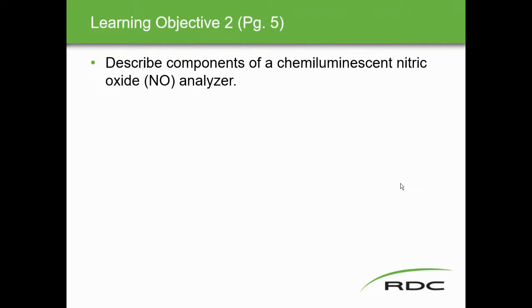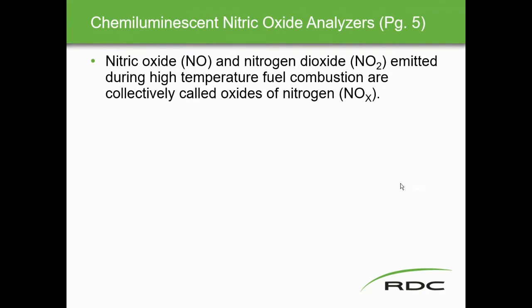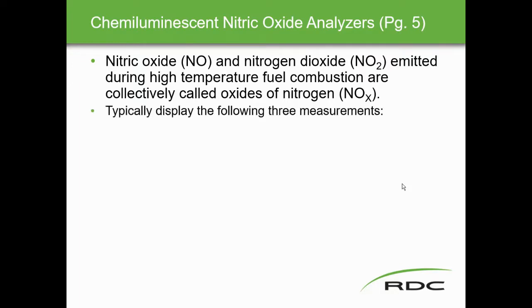Learning objective two: describe components of the chemiluminescent nitric oxide analyzer. Nitric oxide and nitrogen dioxide are emitted during high-temperature fuel combustion in stacks, and are collectively called NOx — oxides of nitrogen. The analyzer typically displays three measurements: NO (nitric oxide), NO2 (nitrogen dioxide), and NOx, which is the combination of NO and NO2.